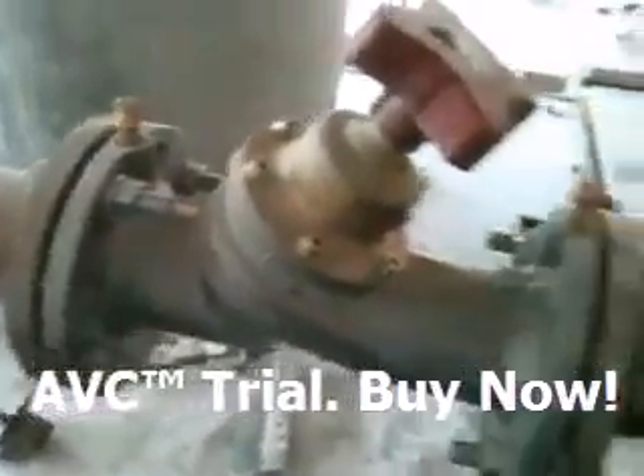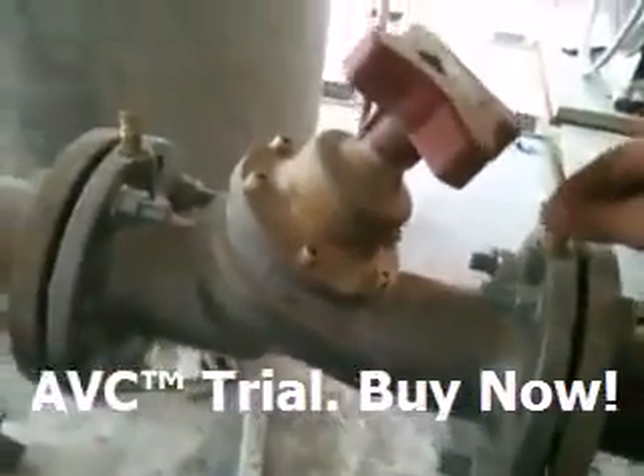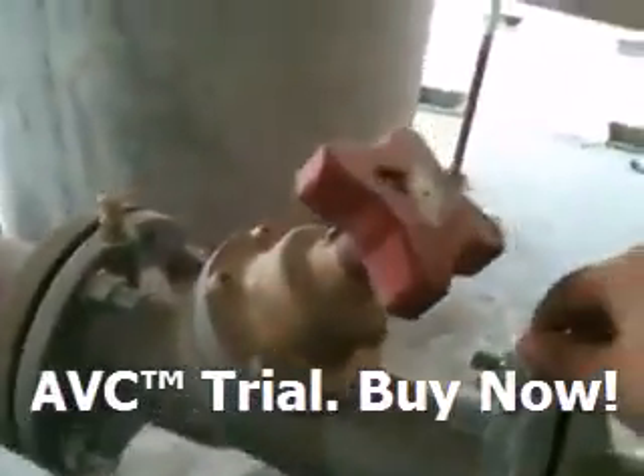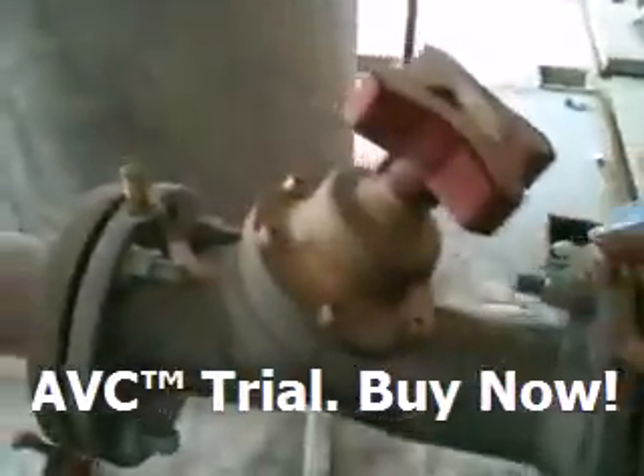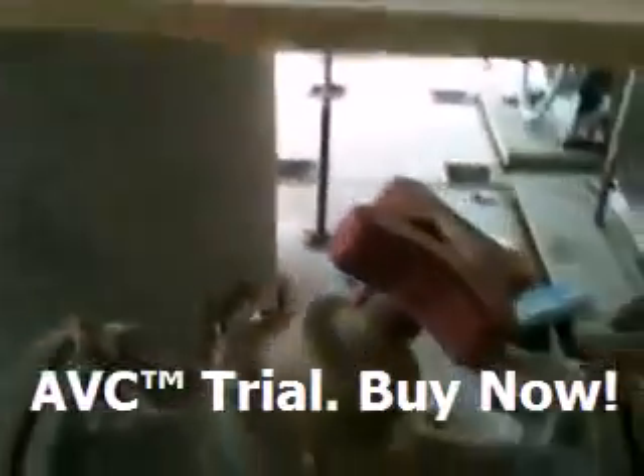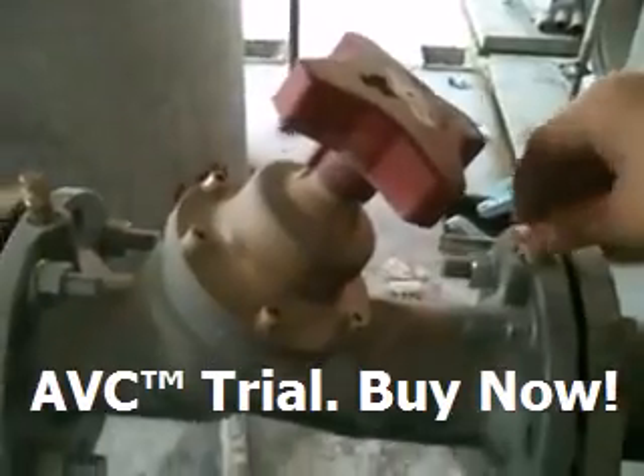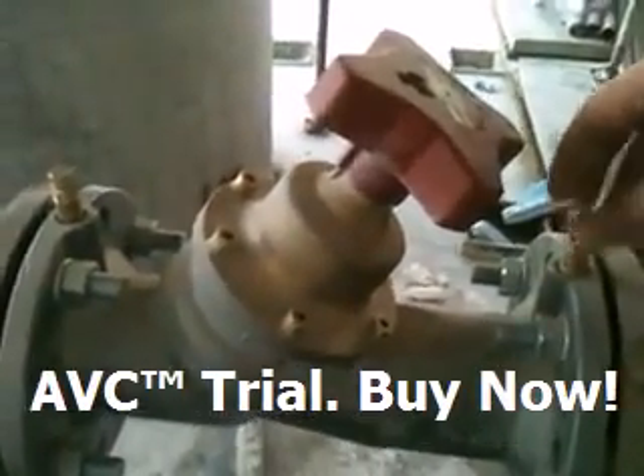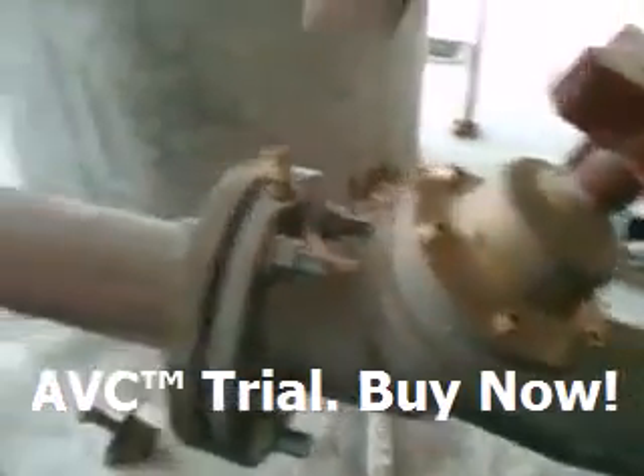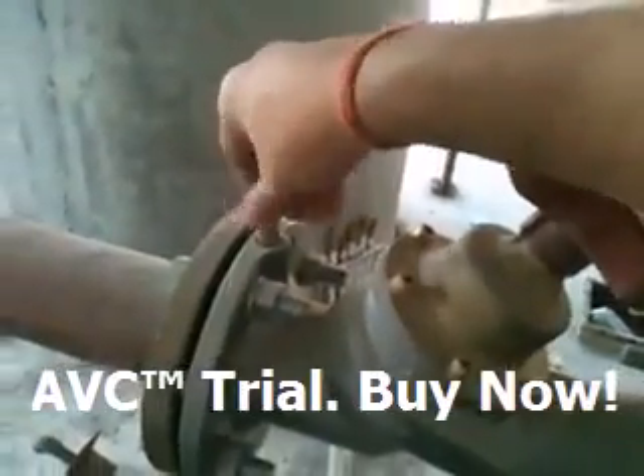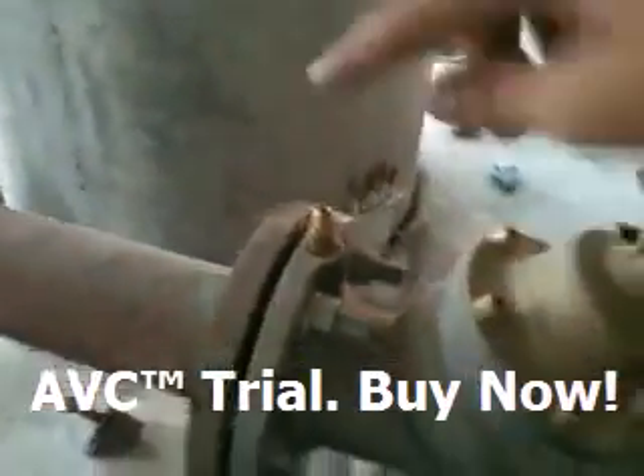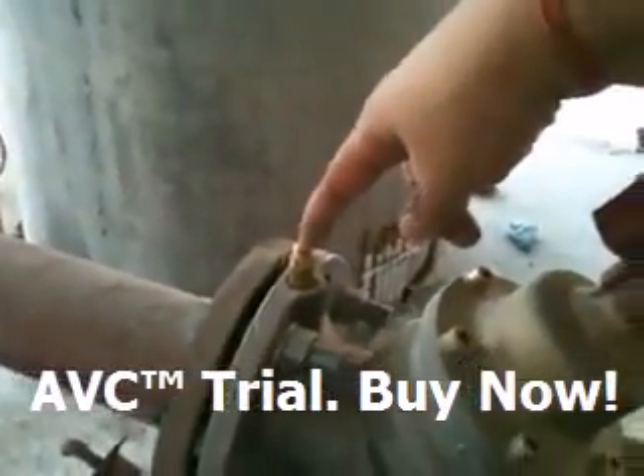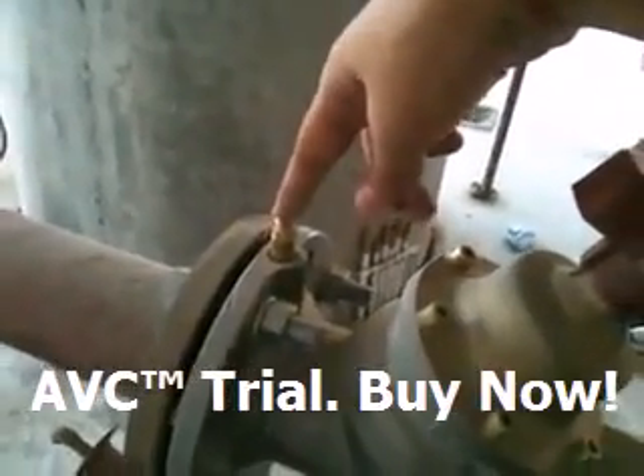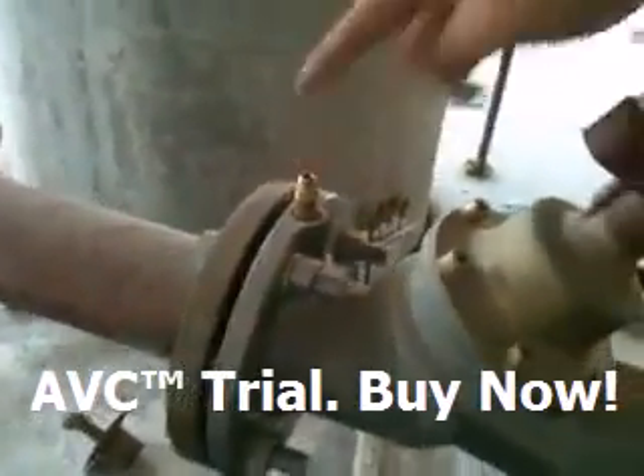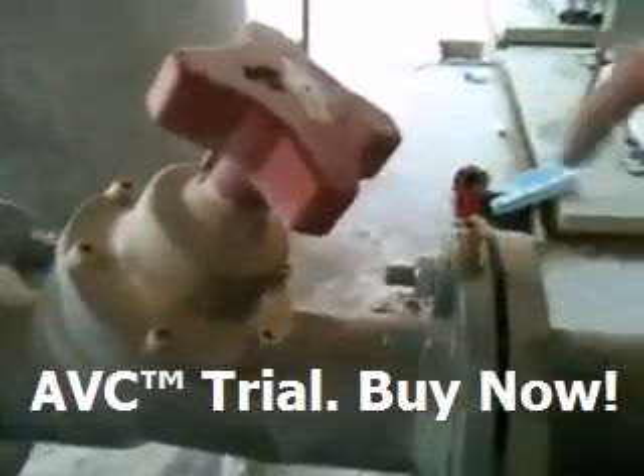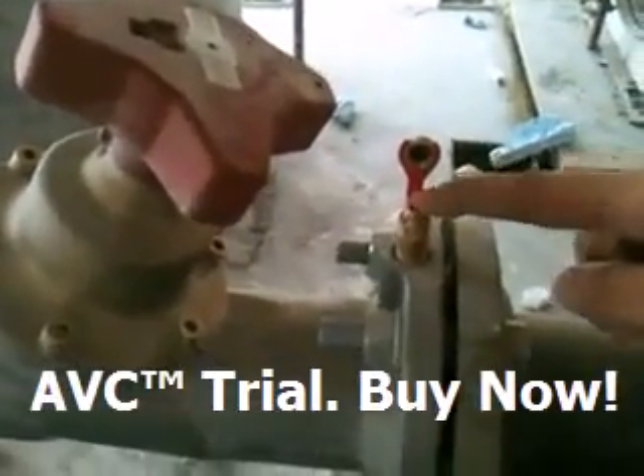From here, this double regulating valve, we can calculate the flow rate. These are the 2 test points - from here we can put our flow meter to check. First we'll put it here to check what the flow rate is, and after regulating with this one we can check what the flow rate is now.